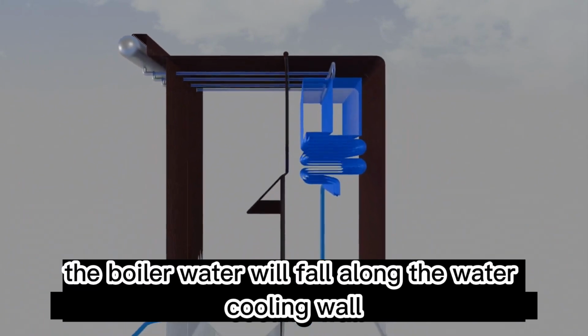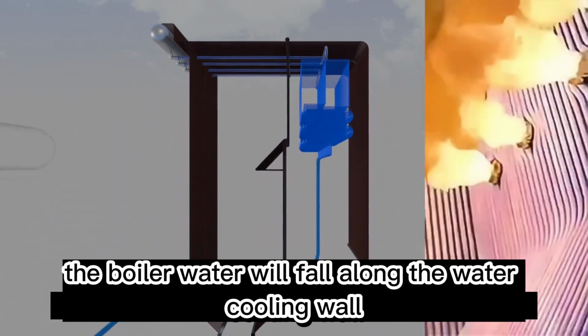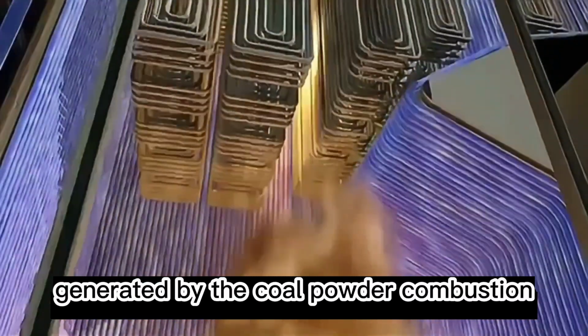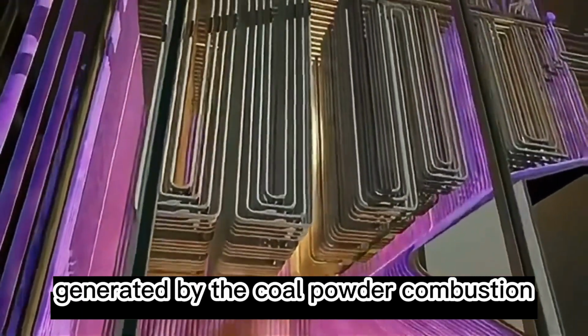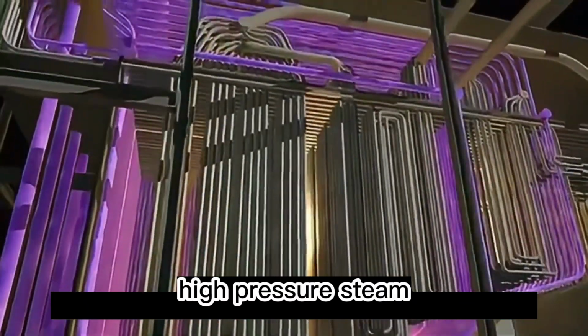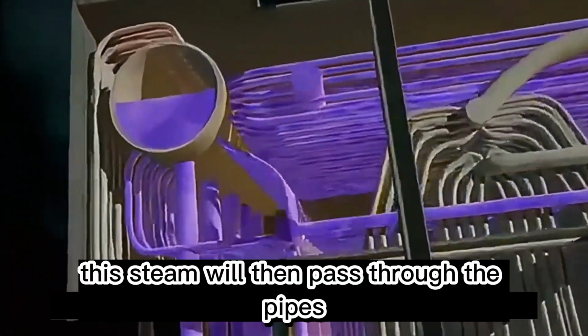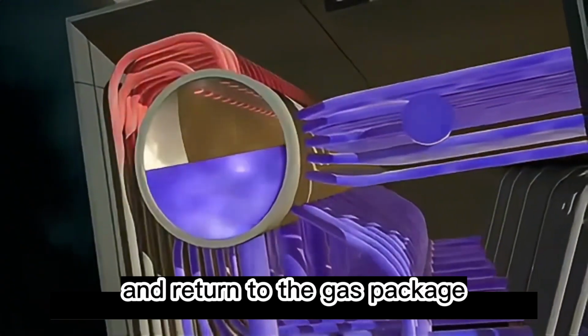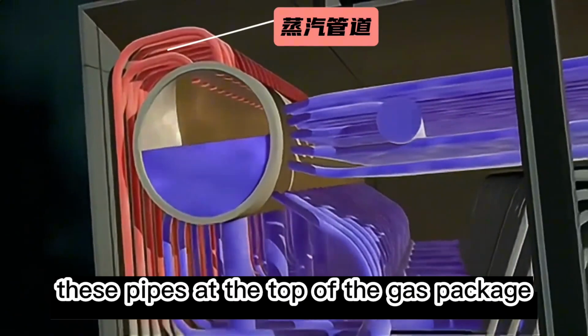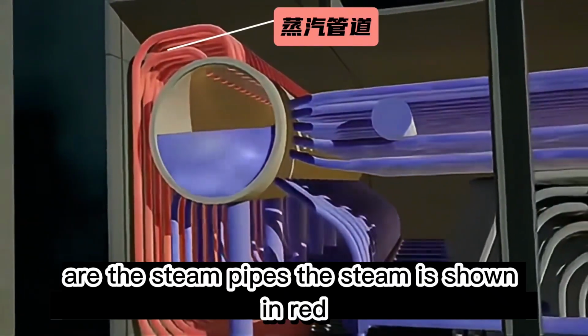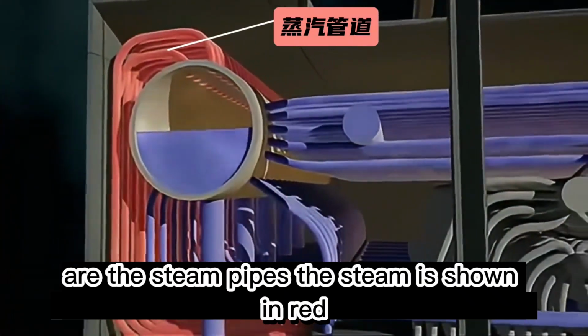The boiler water will fall along the water cooling wall. In the process of flowing, the boiler water will absorb the heat generated by the coal powder combustion. This produces high-temperature, high-pressure steam. This steam will then pass through the pipes and return to the steam drum. These pipes at the top of the steam drum are the steam pipes. The steam is shown in red.